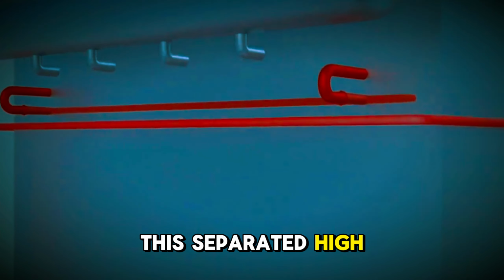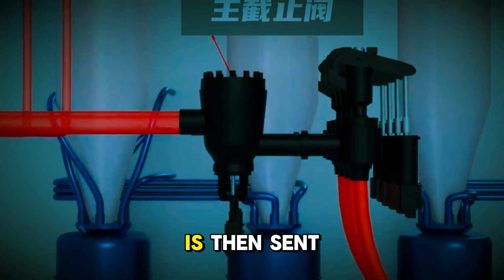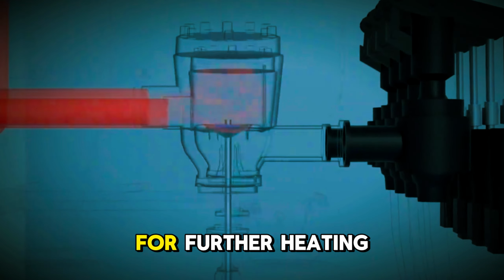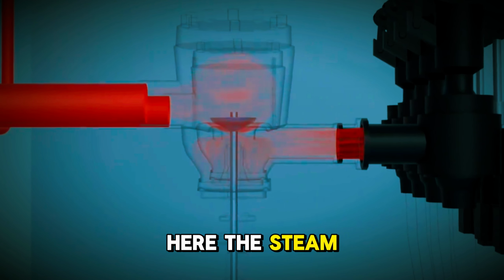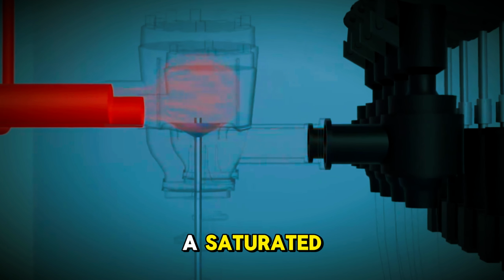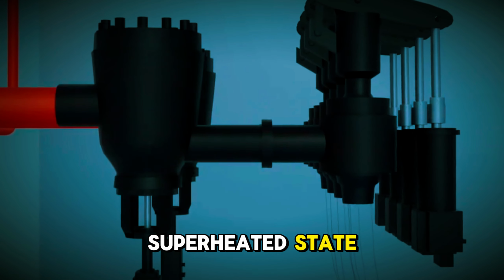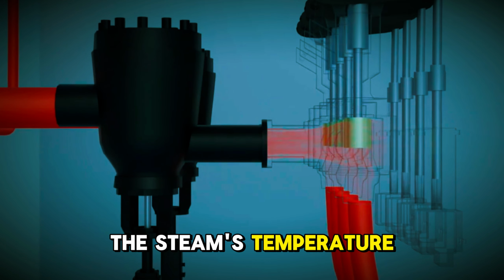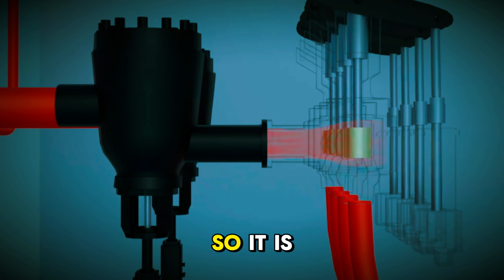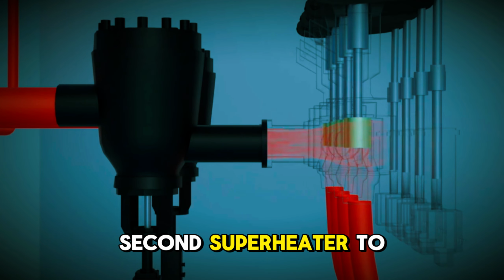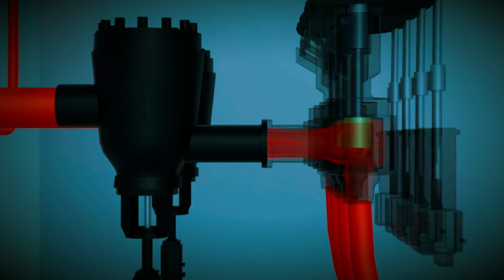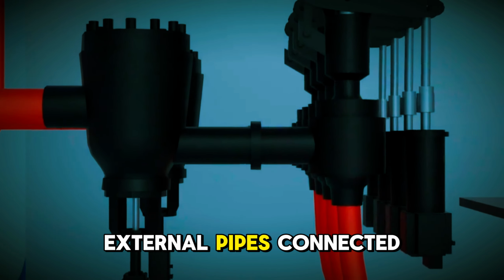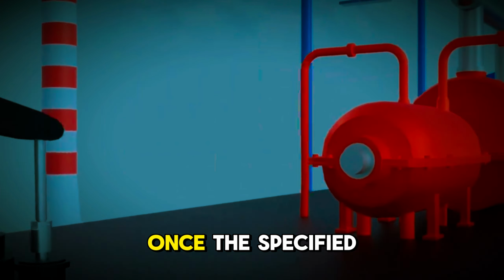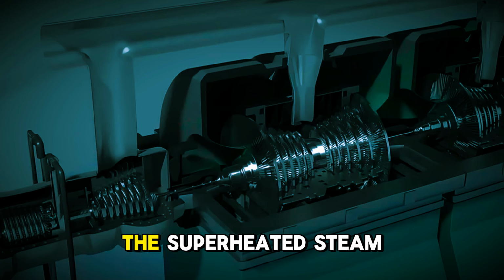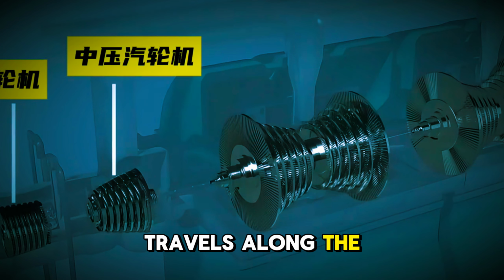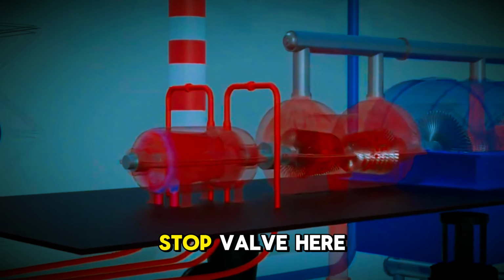This separated high-temperature, high-pressure steam is then sent into the superheater for further heating. Here, the steam gradually transforms from a saturated state to a superheated state. However, the steam's temperature is still not high enough, so it is then sent into a second superheater to continue heating. There are several external pipes connected to the superheater. Once the specified temperature is reached, the superheated steam travels along the external pipes to the main stop valve here.